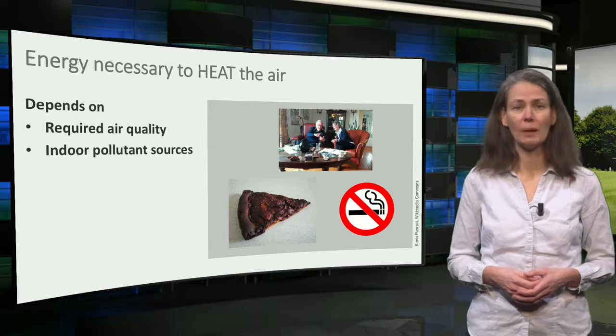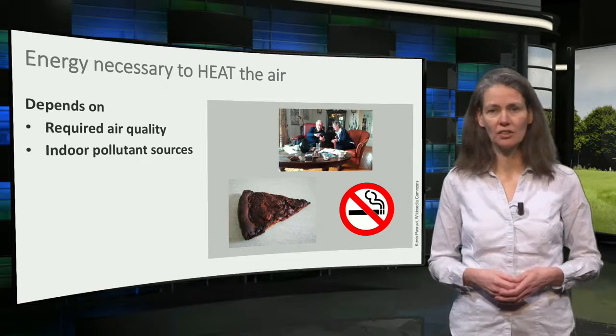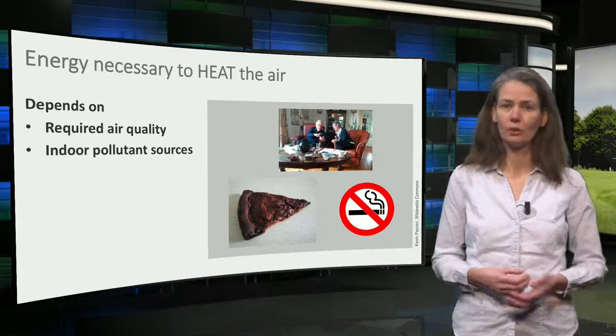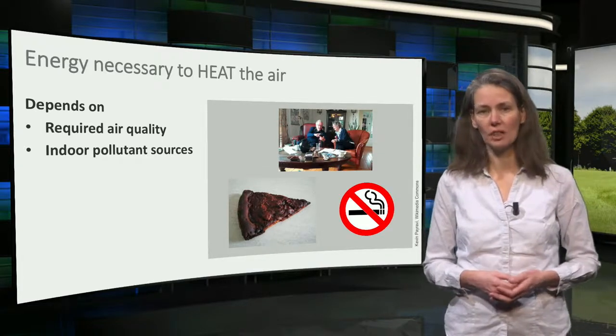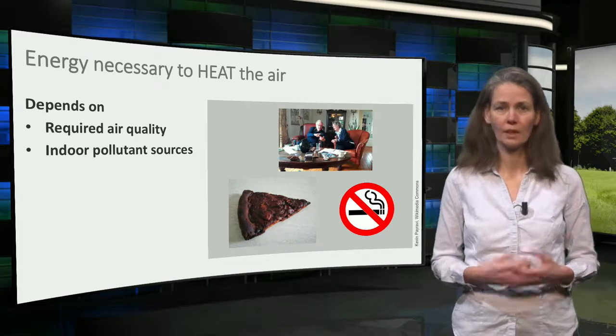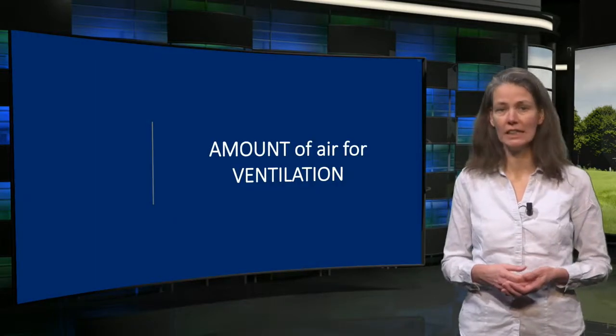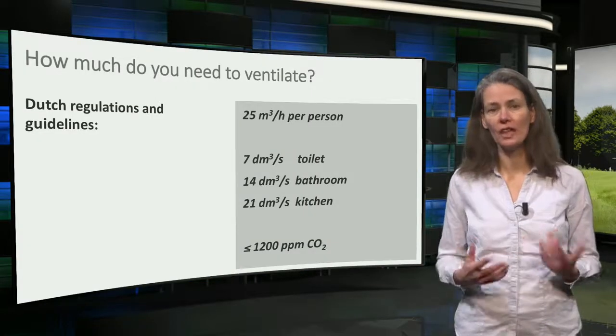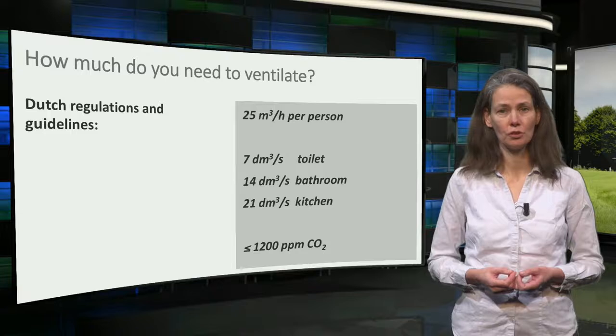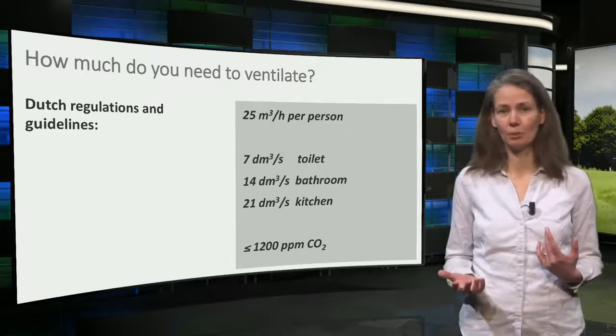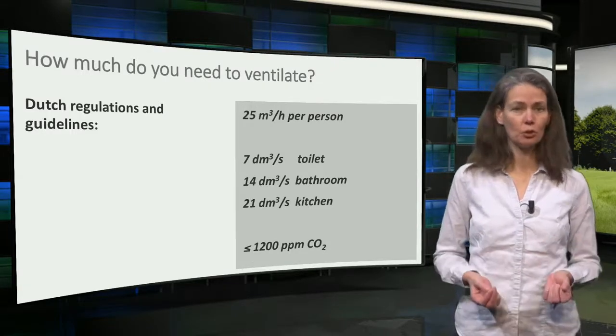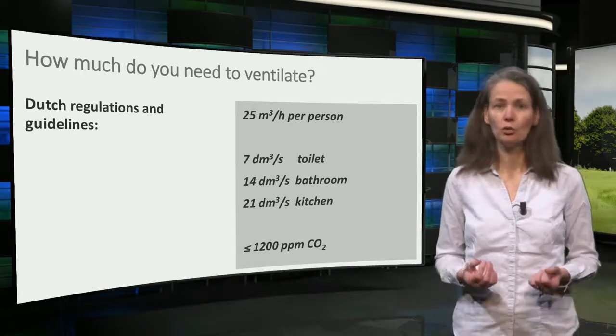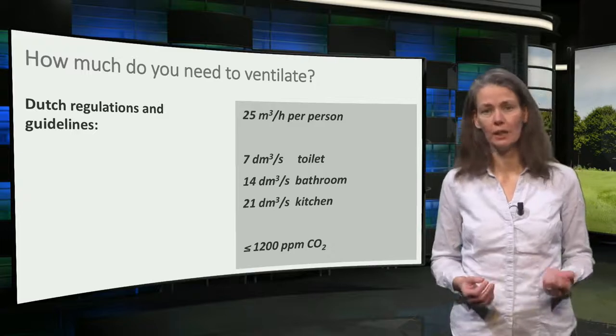The second aspect of the energy demand for ventilation is the energy necessary to heat the air. This amount of energy depends on the required air quality inside and the presence of indoor pollutant sources. The Dutch regulations and guidelines state around 25 cubic meters per hour per person, or different values for toilet, bathroom, and kitchen ventilation. A CO2 concentration of less than 1200 ppm is also advised to ensure a healthy and generally comfortable indoor air quality.